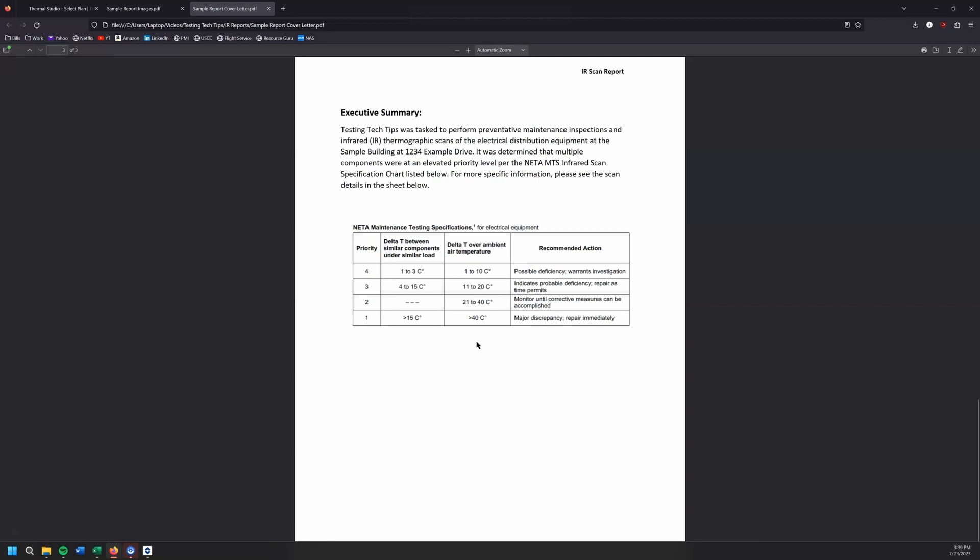There's a lot of things, like if I'm looking at a piece of bus bar that's got like 20 amps of load on it, I shouldn't expect any variation over ambient at all. And if I've got 15C rise over ambient, well, if I've only got like a tiny bit of load on it, that's something I need to address right away. Like it's definitely an issue. So I don't know. I sort of take these with a grain of salt, but the delta T between similar loads like that is generally what I go off of anyway.